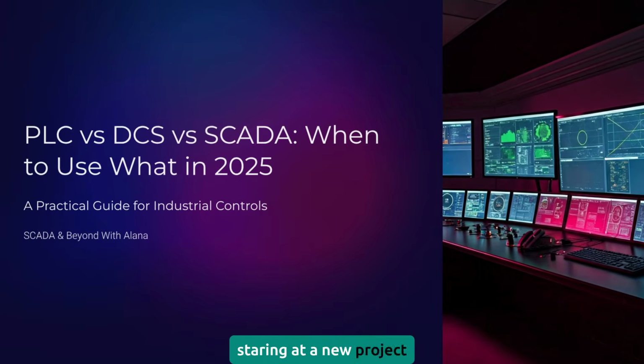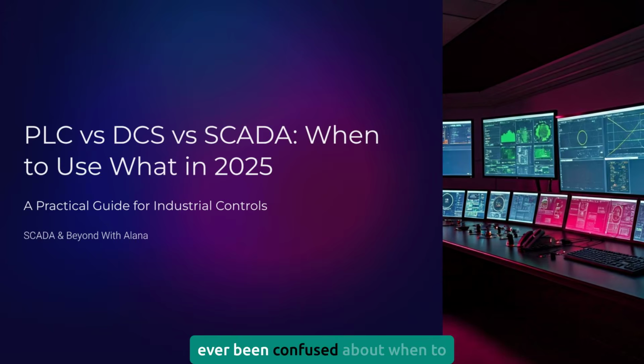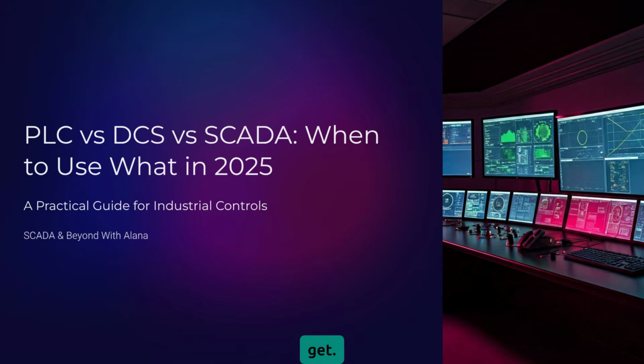So you're staring at a new project spec and wondering, do I need a PLC, a DCS, or SCADA? Or maybe all three? If you've ever been confused about when to use what, you're definitely not alone. After 35 years in the field, this is probably the most common question I get.